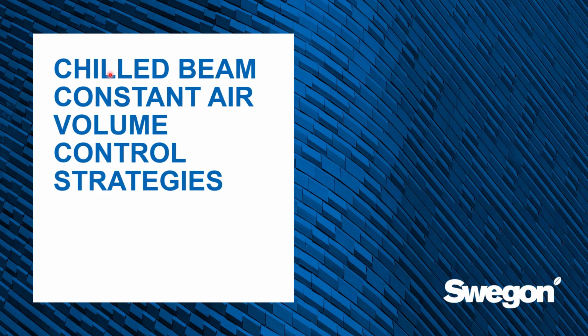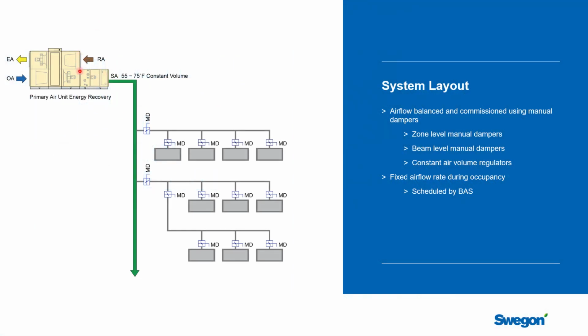In this session, we're going to discuss chilled beam control strategies. In particular, we're going to talk about constant airflow systems. So here's our basic system. We have an air handling unit that's providing the primary air through the supply air ductwork out to each one of the active chilled beams.